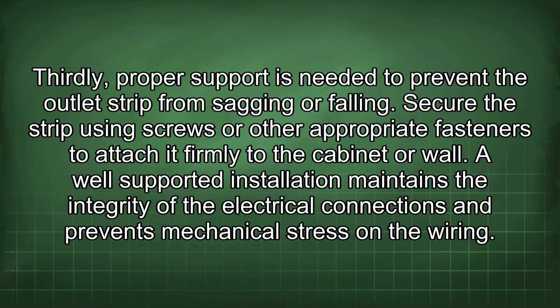Thirdly, proper support is needed to prevent the outlet strip from sagging or falling. Secure the strip using screws or other appropriate fasteners to attach it firmly to the cabinet or wall. A well-supported installation maintains the integrity of the electrical connections and prevents mechanical stress on the wiring.